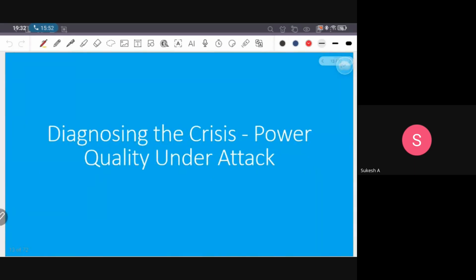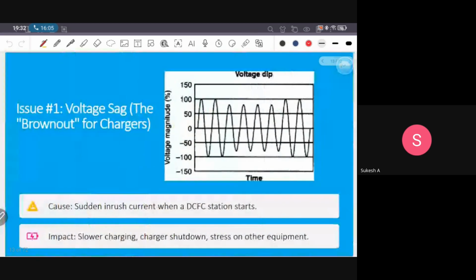And diagnosing the crisis, power quality is under attack. Now let's dissect the specific power quality ailments caused by EV chargers. Understanding this is the key to prescribing the right cure. So the first issue is voltage sag. Voltage sag is nothing but a dip in voltage for a short duration. A number of cycles are dipped from our rated maximum voltage. Here you can see 100 volt is the rated volt.